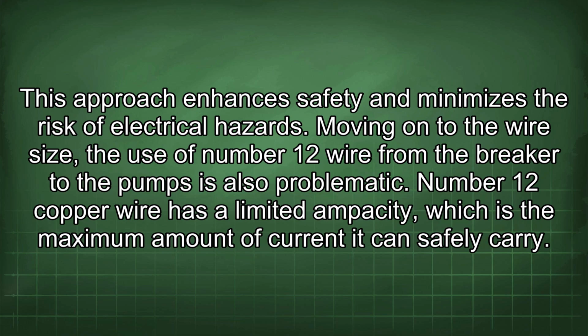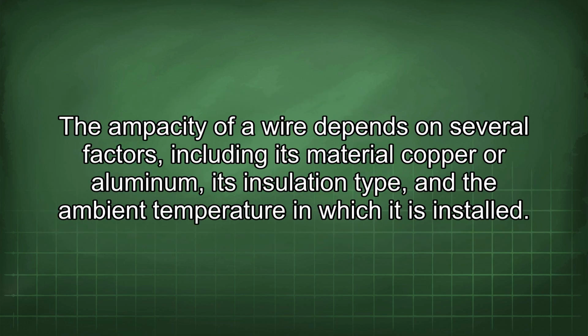Moving on to the wire size, the use of number 12 wire from the breaker to the pumps is also problematic. Number 12 copper wire has a limited ampacity, which is the maximum amount of current it can safely carry. The ampacity of a wire depends on several factors, including its material, copper or aluminum, its insulation type, and the ambient temperature in which it is installed.